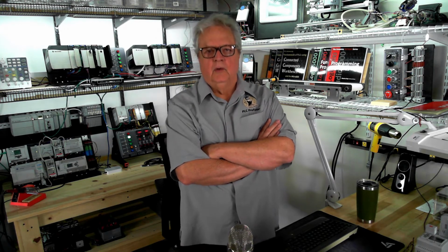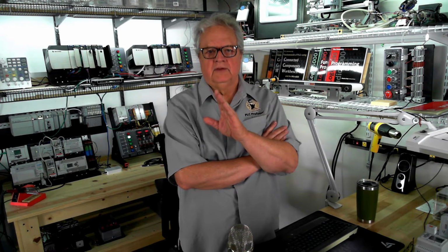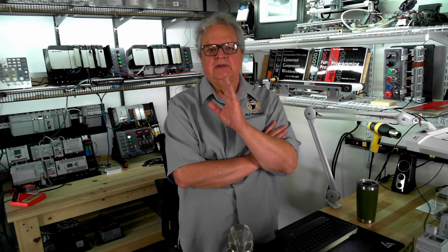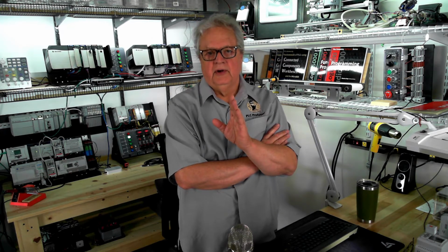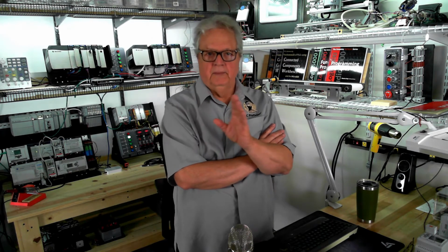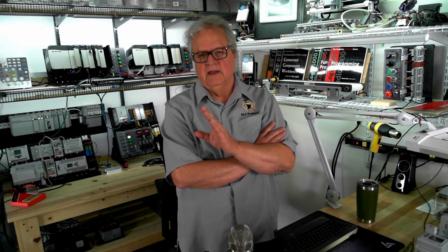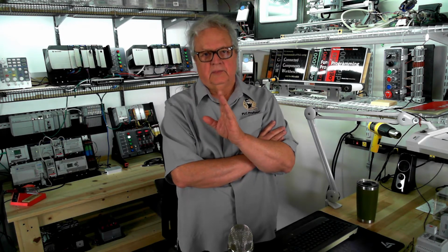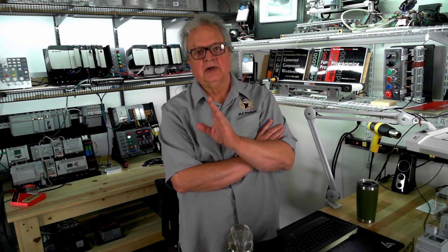In other words, one program scan, the very first program scan that the photo eye bit went on, that is the leading edge of that object on the conveyor. Then there's the period of time that it's blocking the optical path as it travels. Then there's another instantaneous event, and that is when it clears the optical path of the photo eye. That is, the previous scan, the photo eye was blocked, and on the next scan, it's clear.